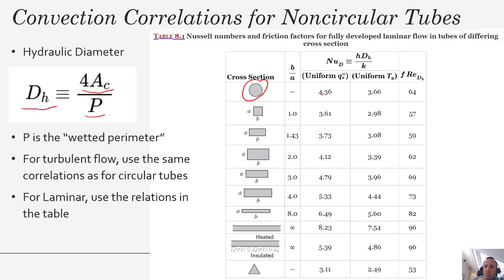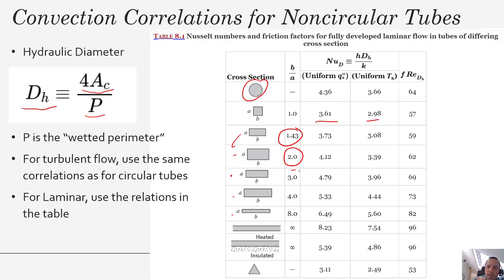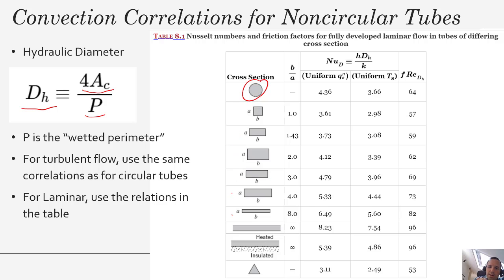For a circular cross-section with uniform flux, Nu is 4.36; with uniform surface temperature, Nu is 3.66. For a square channel these values change. For a rectangular channel there are many different forms depending on the aspect ratio — the length divided by the width — and you may need to interpolate if your aspect ratio doesn't match exactly. When back-calculating your heat transfer coefficient H from the Nusselt number, the diameter you use is the hydraulic diameter.